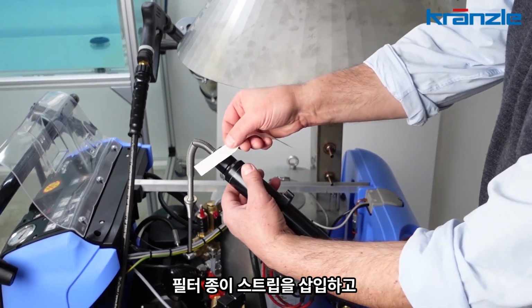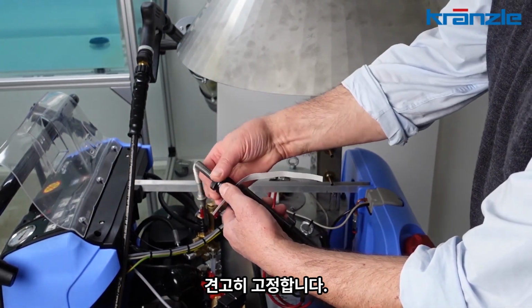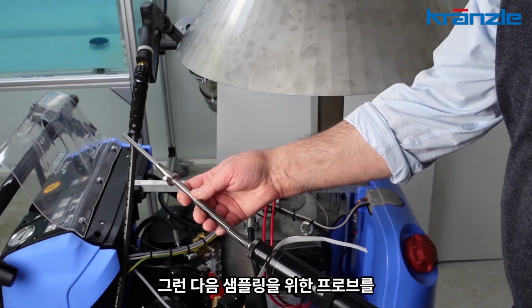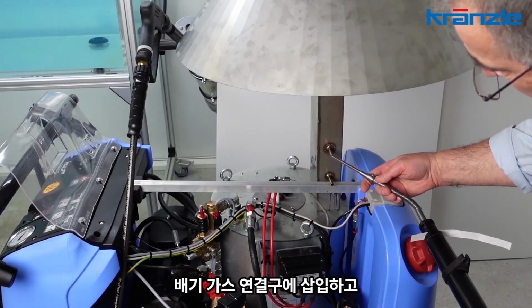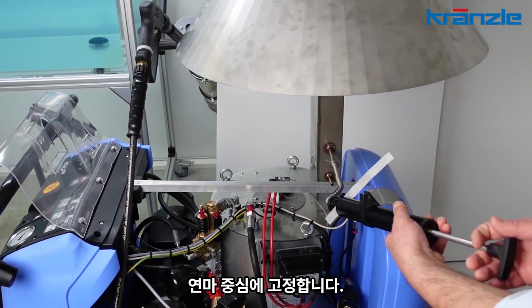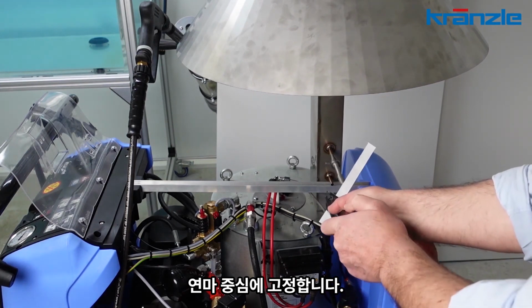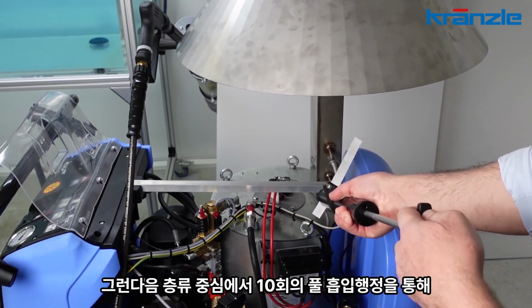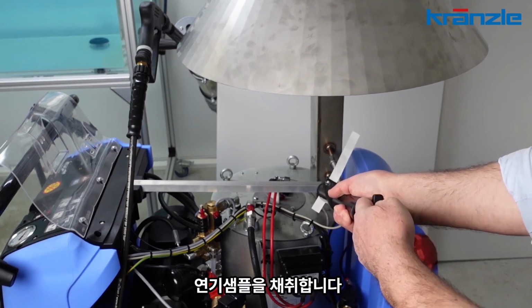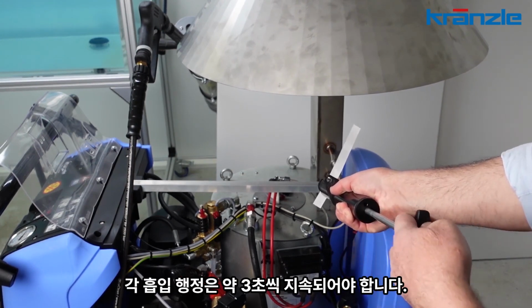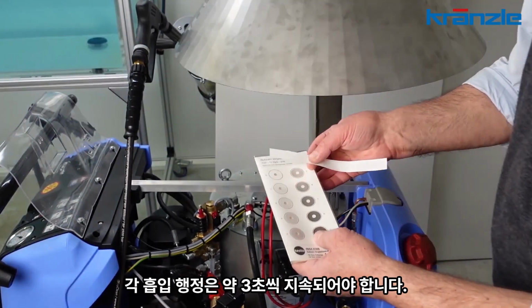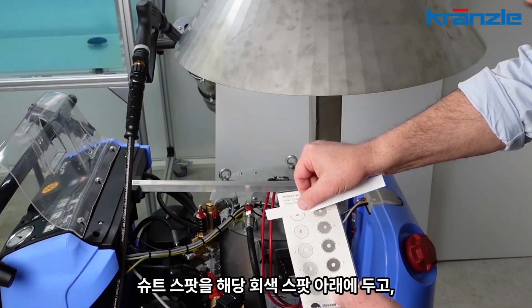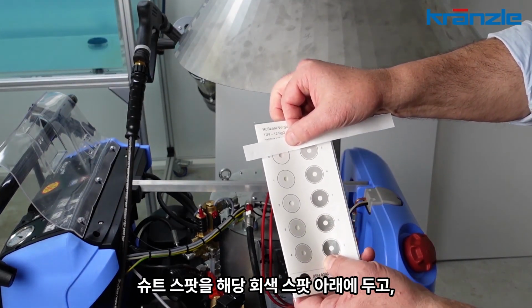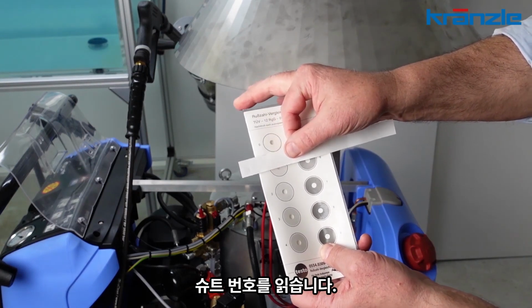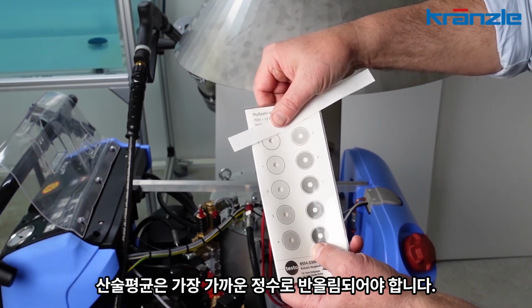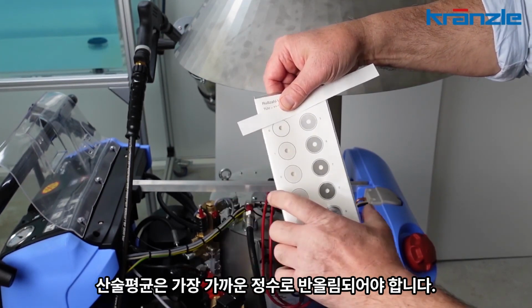Then insert the filter paper strip into the slot opening of the soot measuring device and clamp it tight. Then insert the probe for sampling into the exhaust gas connection and clamp it in the middle of the flue gas core flow. Then take the flue gas sample by implementing 10 full suction strokes in the core stream. Each suction stroke should last approximately 3 seconds. Then evaluate with the comparison scale, holding the soot spot under the corresponding gray spot and read the soot number. At least 3 measurements are required and the arithmetic mean should be rounded to the next full number.